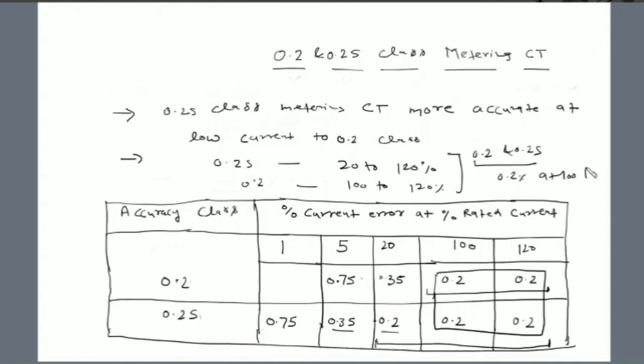Both 0.2 and 0.2S class CT have 0.2% current error at 100% and 120% of rated current, but 0.2S class CT has higher accuracy even at lower values of current. So 0.2S class CT accuracy is better compared to 0.2 class CT, and that is the reason for tariff metering and revenue metering we use 0.2S class CT compared to the 0.2 class CT.